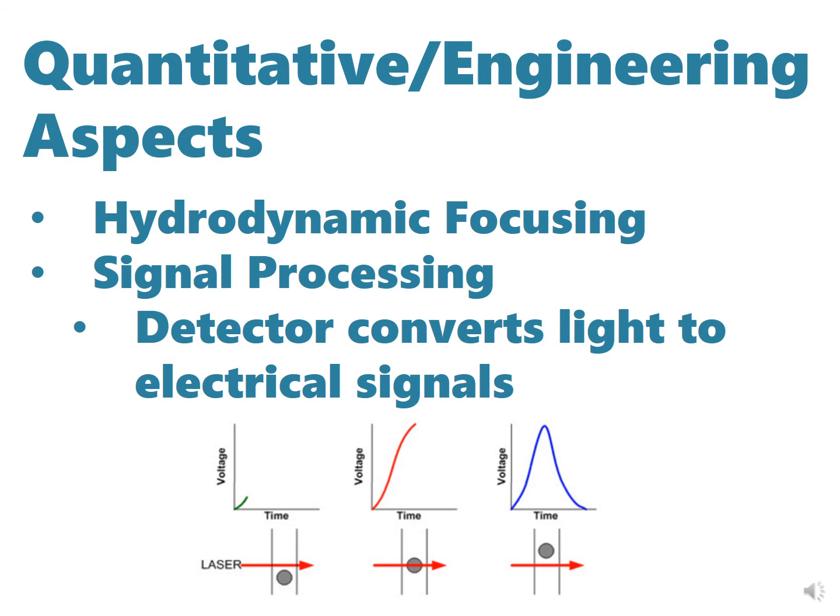The engineering aspects related to flow cytometry and FACS are related to hydrodynamic focusing where we can change the shear rates as well as the sample flow rates to get the perfect diameter for a single cell line. And the signal processing related to electronic systems gives us the detector which converts light to electrical signals based on a few parameters.